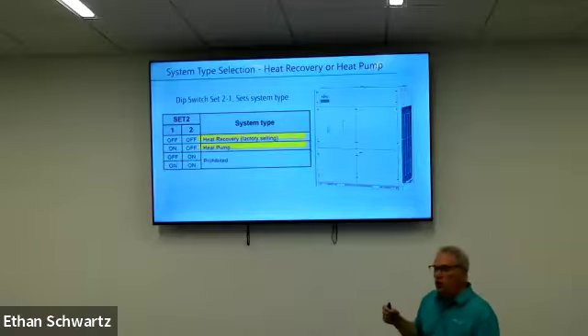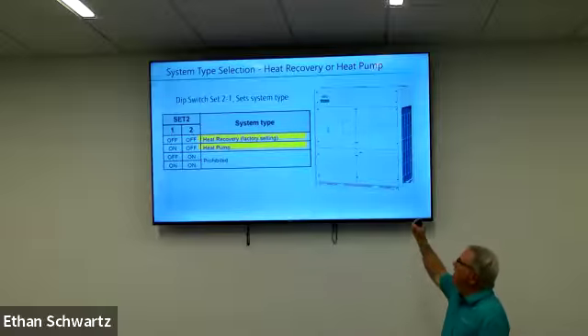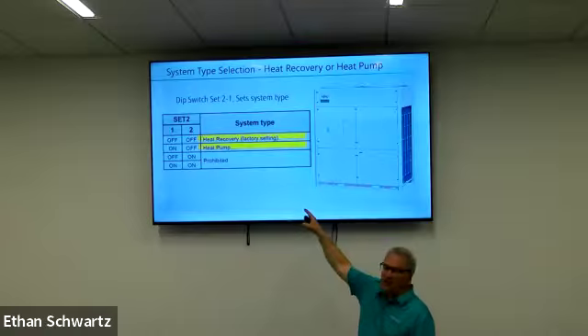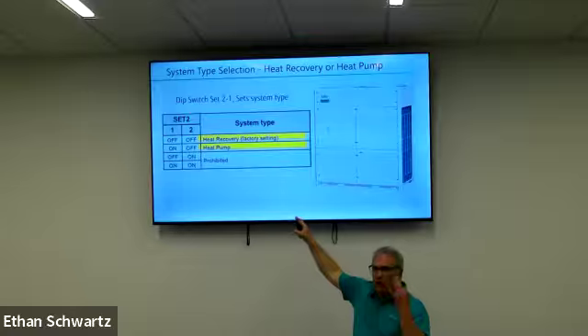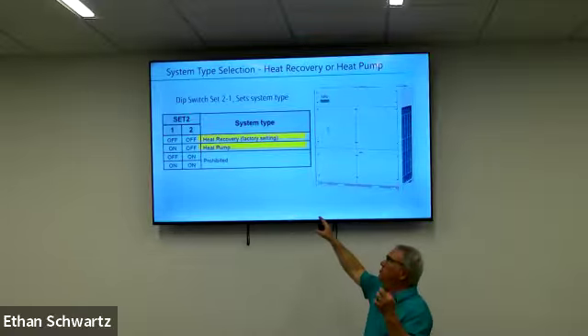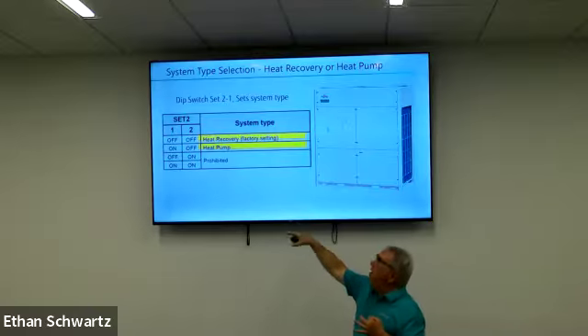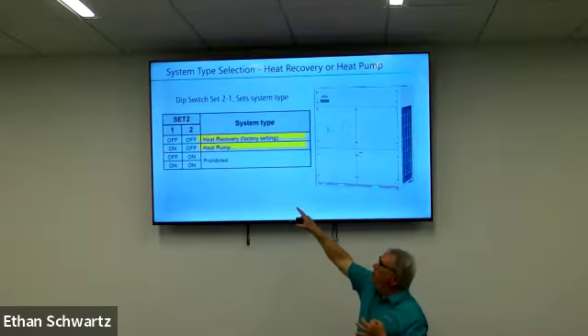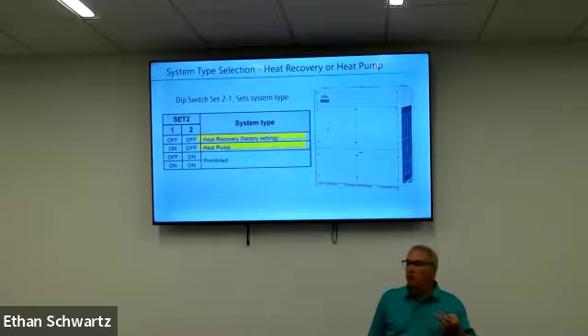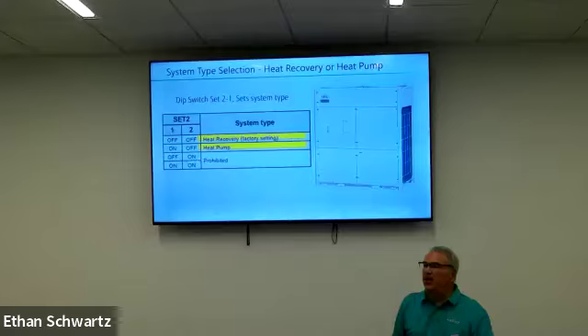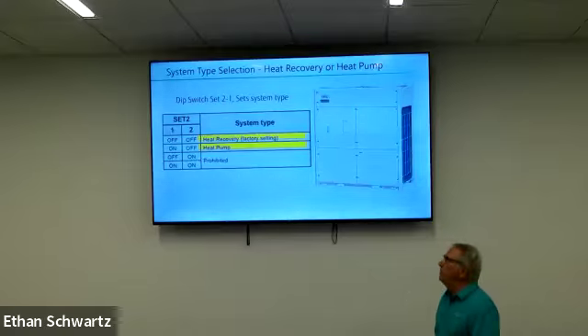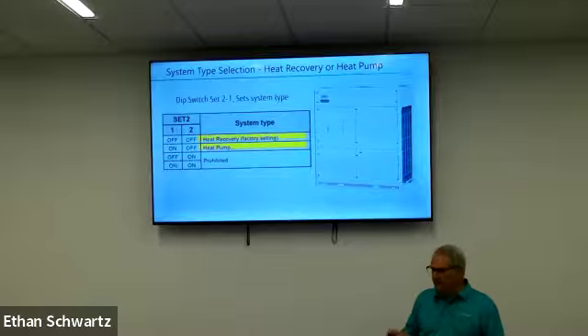All right, then the U in the number means that this is universal. It comes factory set as a heat recovery using 3 pipes: liquid line, suction line, and hot gas line. But then if you're going to do a heat pump, you need to go to set 2, which is a dip switch. We talked about it in the training, and we tell it, hey, I'm putting you in a heat pump application, even though you came from the factory set to heat recovery, it's only heat pump. Make sense? Okay.